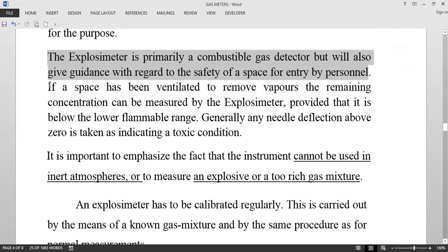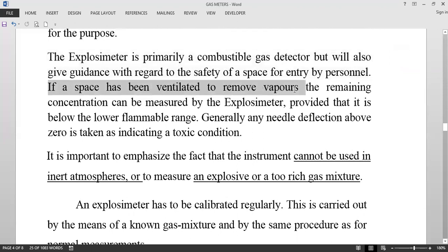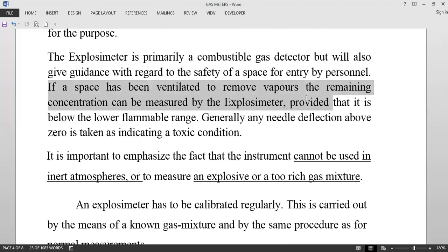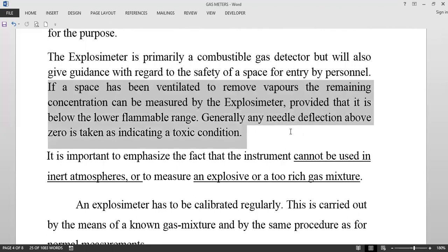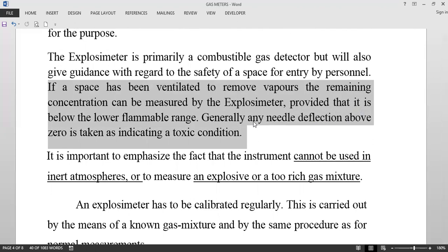If the space has been ventilated to remove vapors, the remaining concentration can be measured by the explosimeter, provided that it is below the lower flammable range. Generally, any needle deflection above zero is taken as indicating a toxic condition. You have to keep in mind that it is used to measure gases only in low concentrations, when the space is not inert and there is sufficient oxygen.